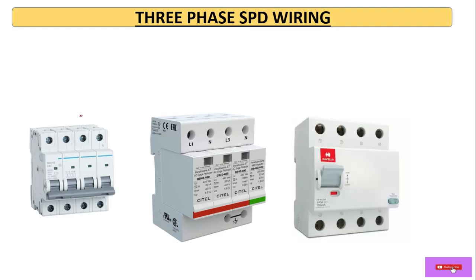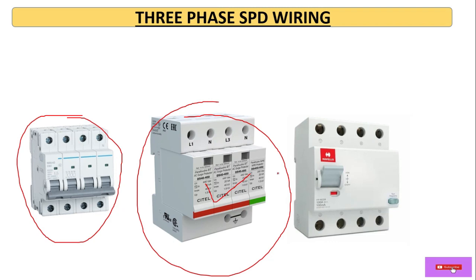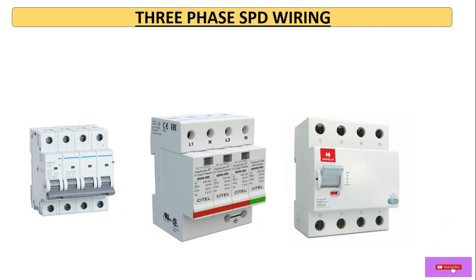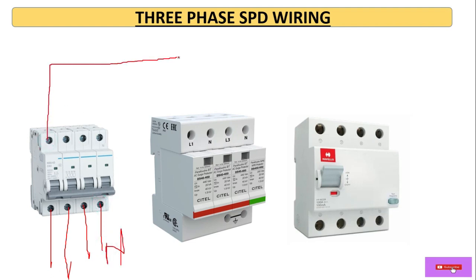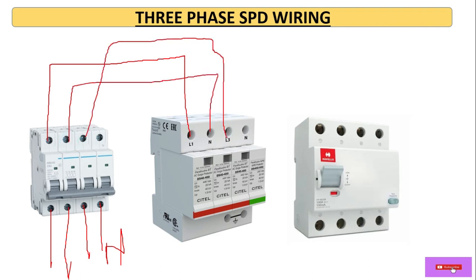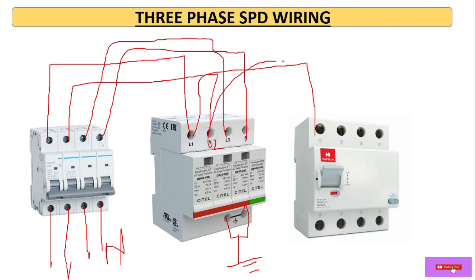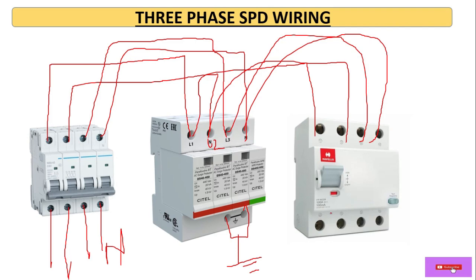Now let's look at the three phase SPD, which is similar to the single phase connection. Here we have taken a four-pole MCB, a four-pole SPD, and a four-pole RCCB. We connect R, Y, B, and neutral from the output of the MCB to the SPD terminals L1, L2, L3, and neutral. The earth terminals are connected to earth. From there it goes to the RCCB and then to the loads. This is how it is connected in a three-phase system.